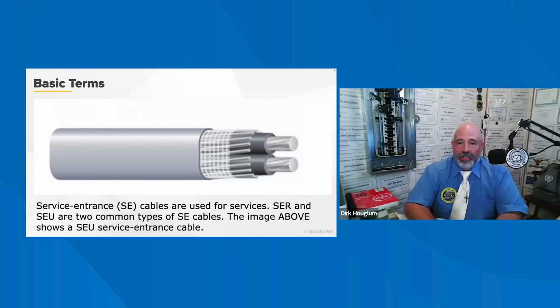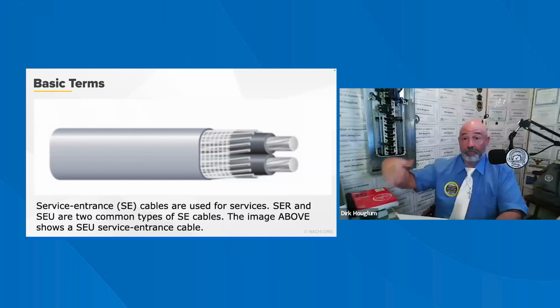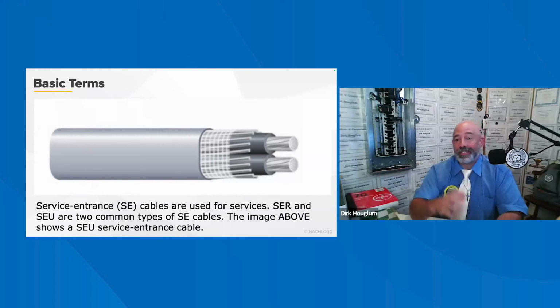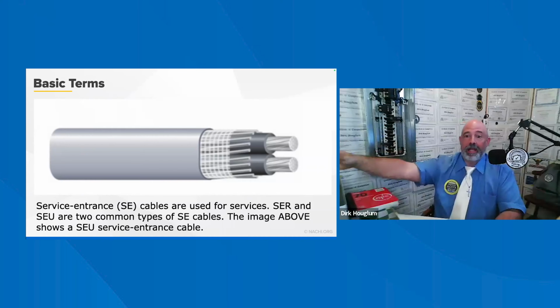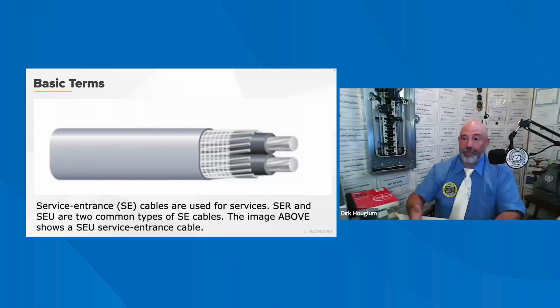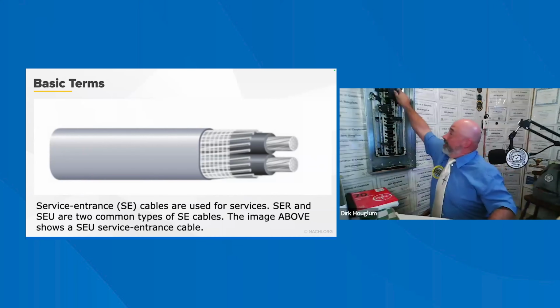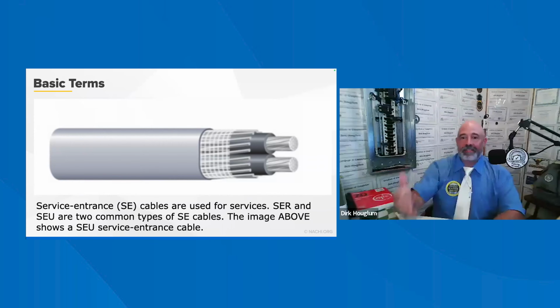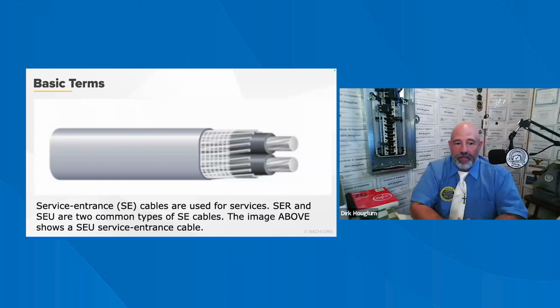The SE, or the service, the conductors and equipment for delivering energy from the service utility to the wiring system of the home. Electrical service is the general term used to refer to all electrical service conductors and equipment. The service begins at the load end of the service drop or the lateral and ends at the panel board cabinet that houses the main disconnect, which would be this guy right there. Okay. The SE and SEU cables, you can see it right in that diagram right there.